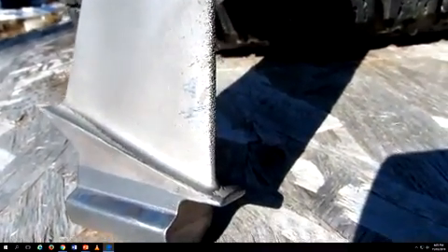This one could be fixed, but because of the root wear, we junked it. This is why intake air filtration is so important for an industrial turbine engine. They run for much longer periods of time between maintenance than an aircraft engine.